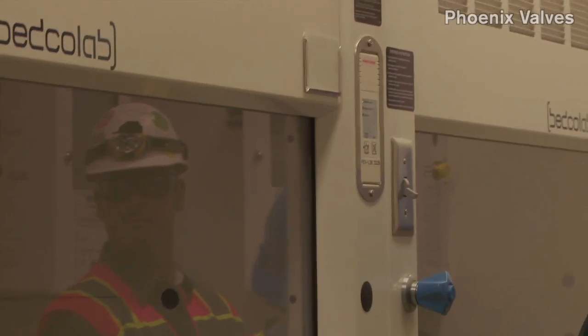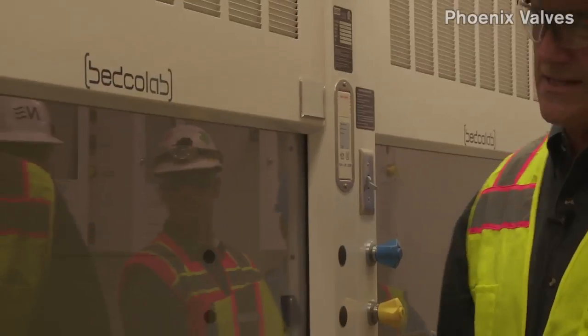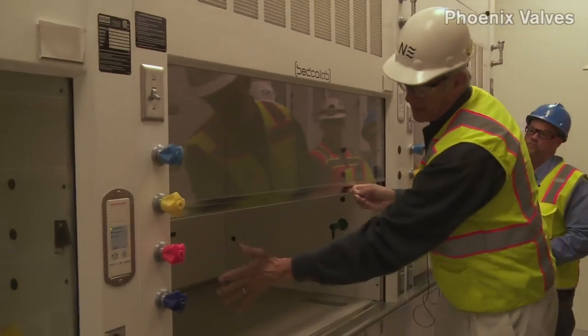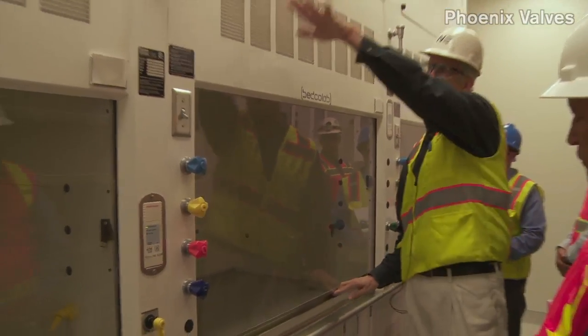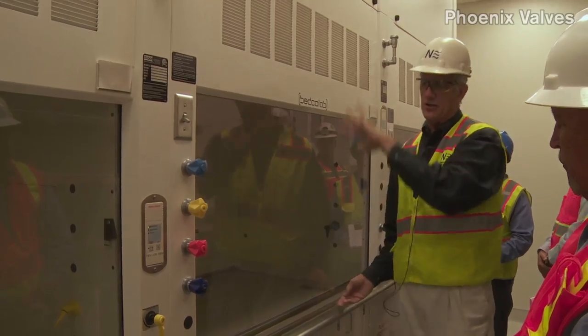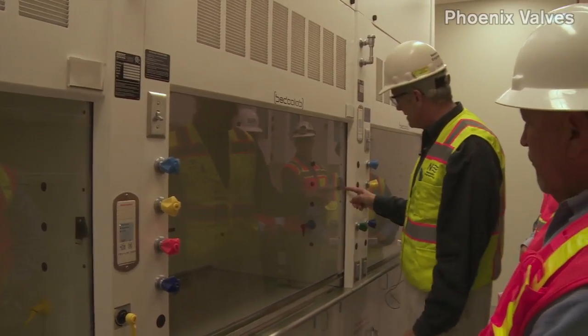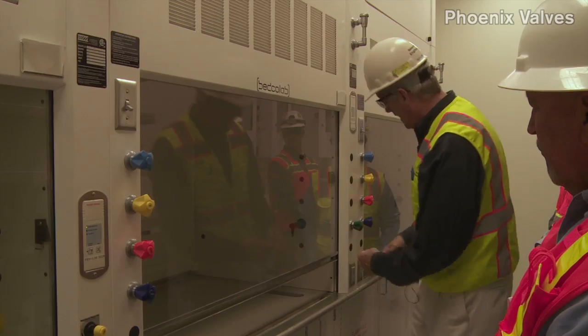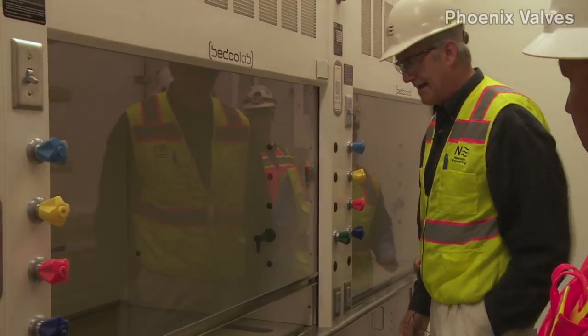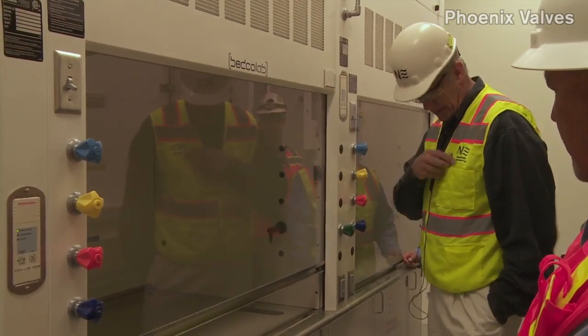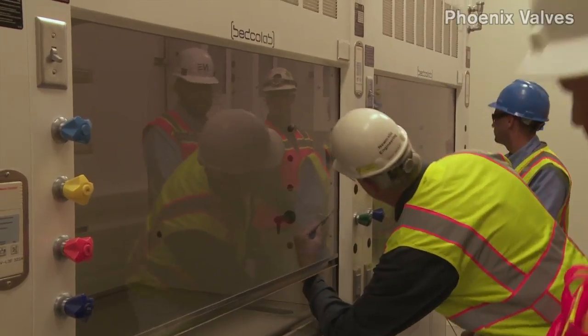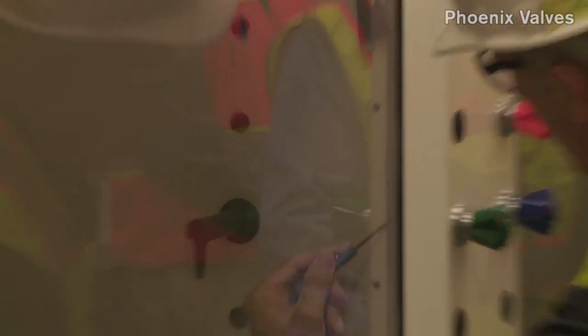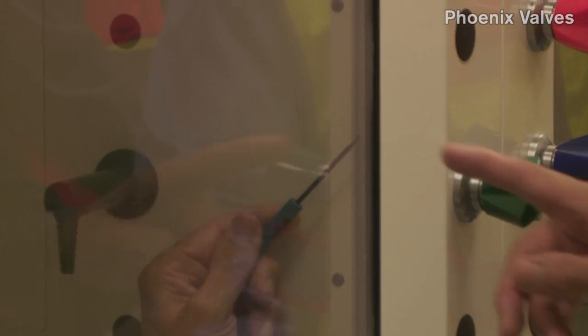Notice the green light here stays on all the time. You raise and lower the sash. Again, when the sash is up, the air goes here. When the sash is down, the air comes over the top. The flow of the air never changes. The hood is only designed to get you to here. We have attached to this hood, not really very visible, a vertical sash sensing cable. I'm going to pull it out there. You see that cable there? That's our sash sensor cable.